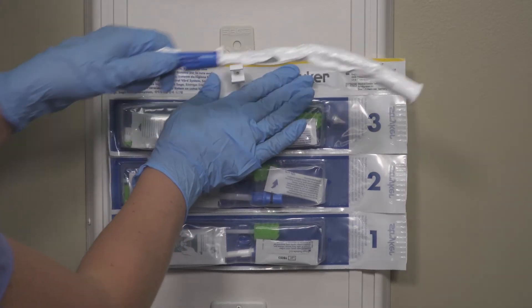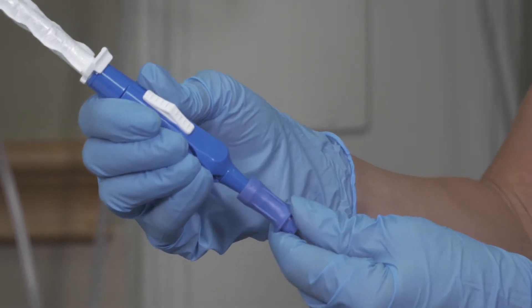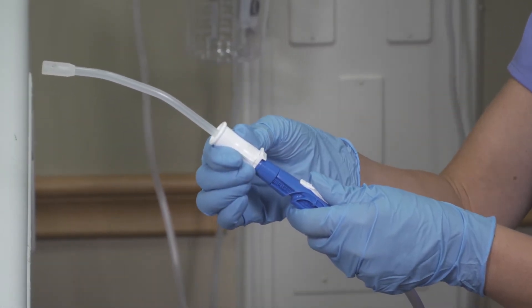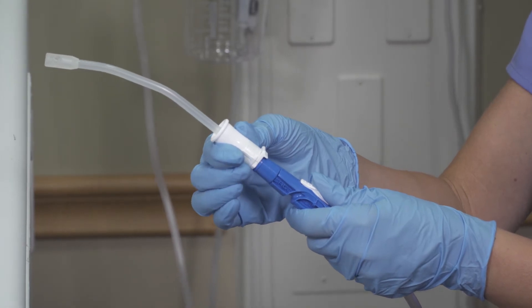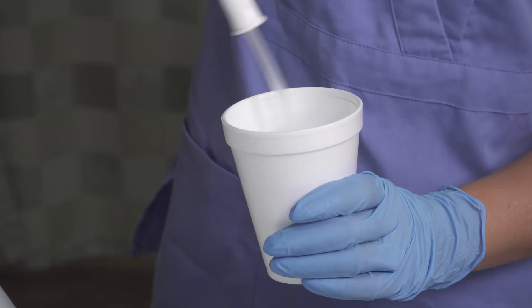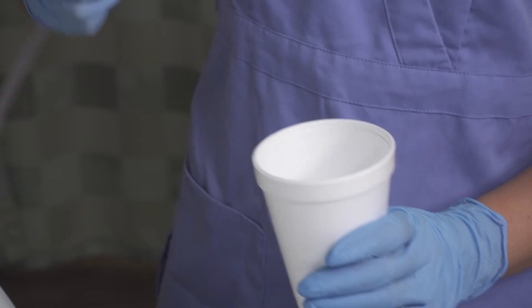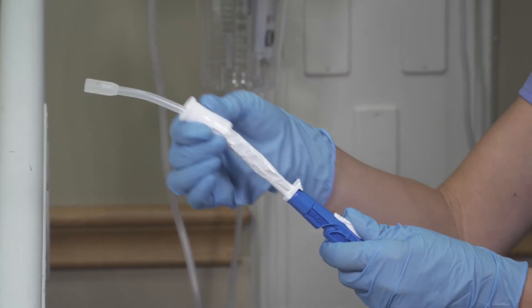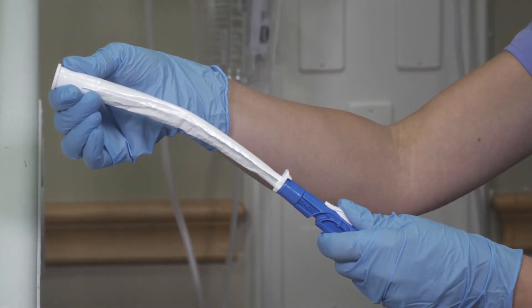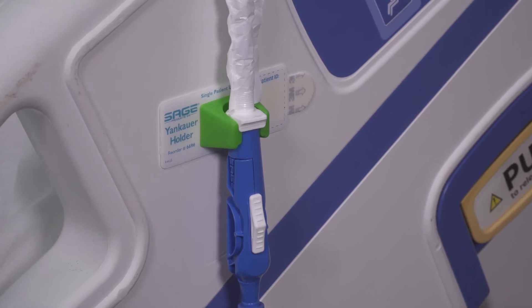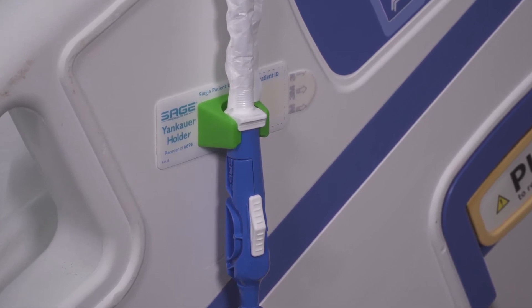Detach the covered yankauer and connect it to the tubing. To use the covered yankauer for removing oral debris and secretions retract the sleeve all the way down until the cap locks in place. Slide the switch to the on position. After each use rinse to clear the line. When finished slide the suction switch to off and pull the sleeve up over the tip. Keep the yankauer attached to the suction line except when using other suction tools and store when not in use.